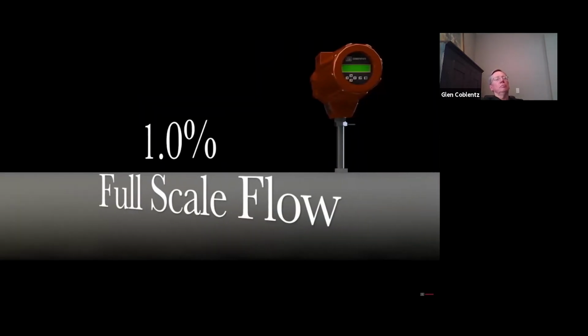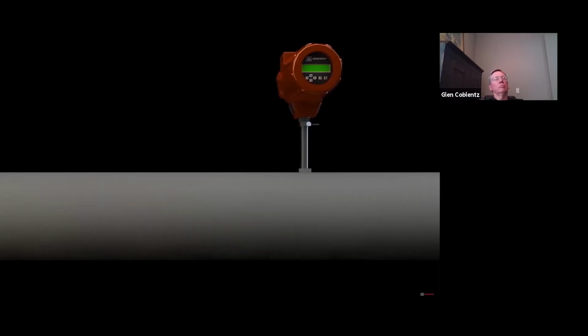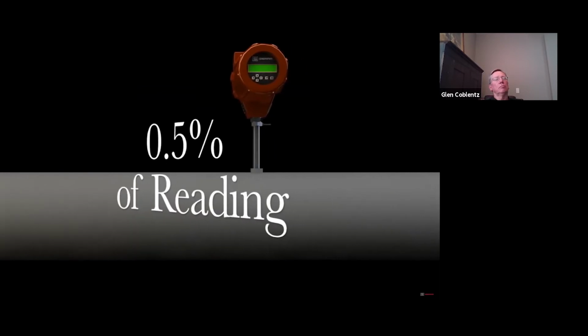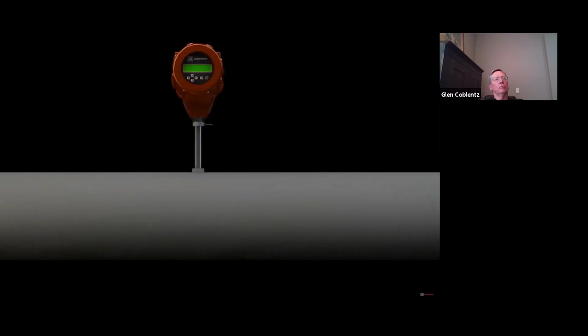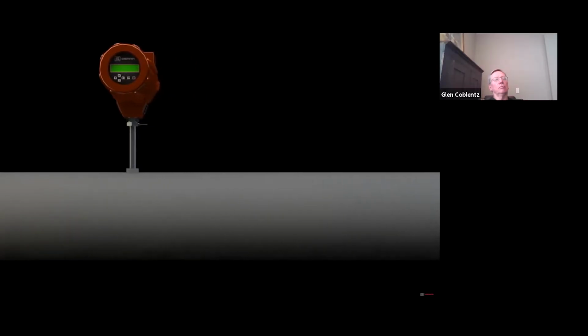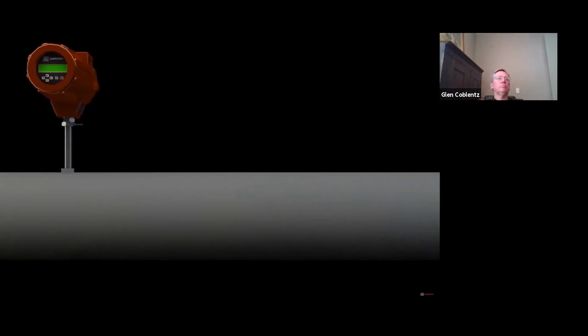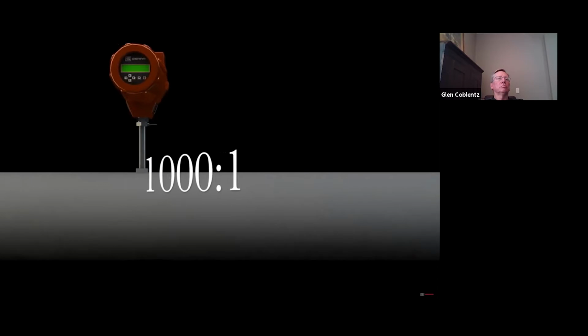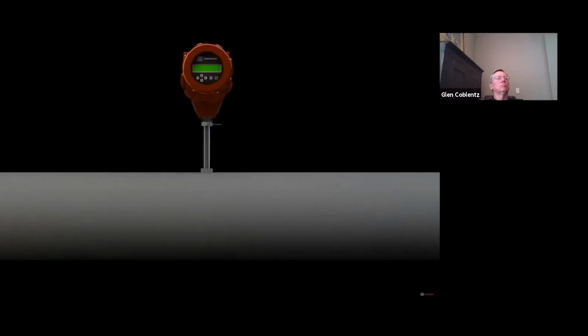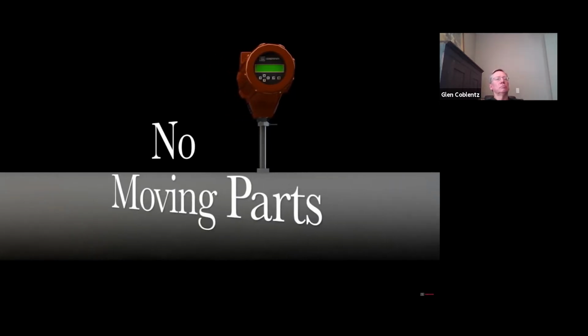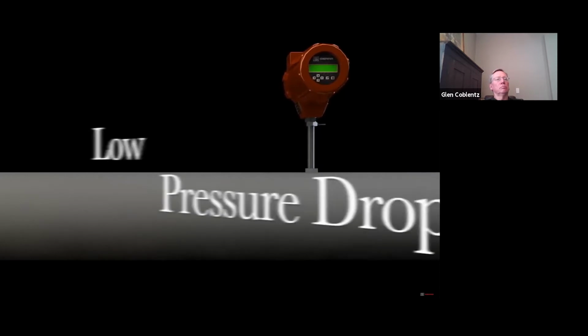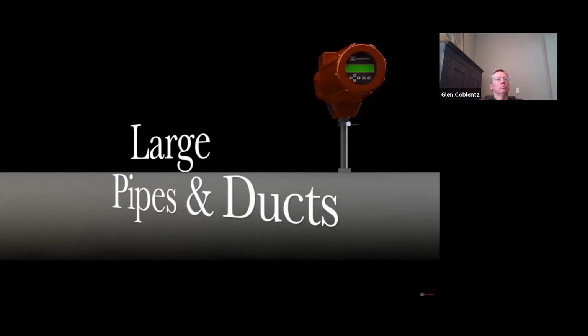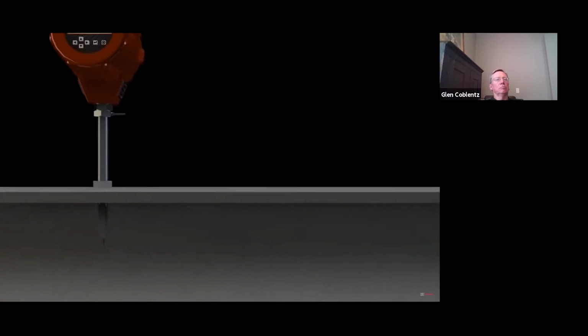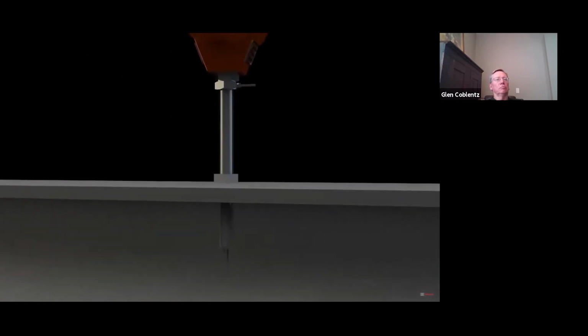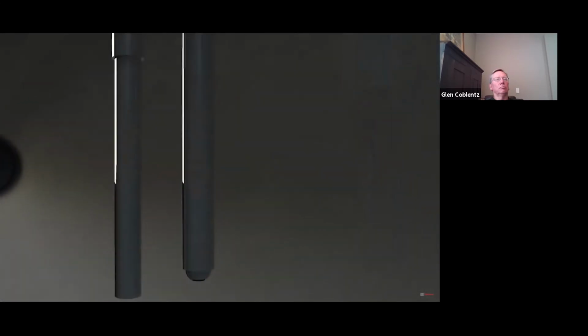Standard accuracy is 1% of full-scale flow, but recent innovation, as with Sierra's Quadratherm flow meter, has pushed accuracy to 0.5% of reading, rivaling that of Coriolis meters. Thermal flow meters are often much more economical than other mass flow meters and have become extremely popular due to high turndown, up to 1,000 to 1, giving the ability to measure very low flows up to very high flows with the same instrument. Since they are rugged and reliable, have no moving parts, are easy to insert via hot tap, have negligible pressure drop, and offer an economical solution to large diameter pipes and ducts, thermal technology has been rapidly adopted over the last decade. So, how does this amazing technology work? In this cutaway view of a typical pipe, the sensor probe is inserted into the center line of the flow.